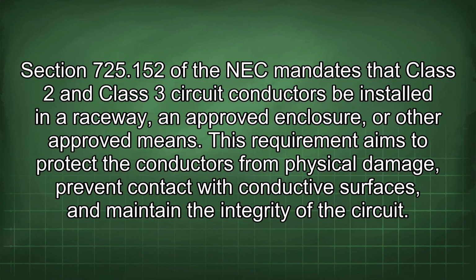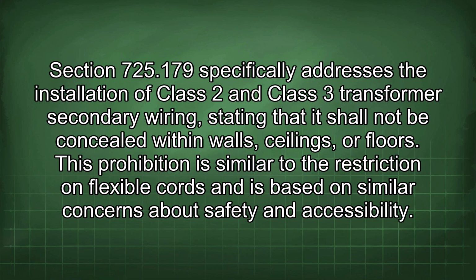Section 725.152 of the NEC mandates that Class 2 and Class 3 circuit conductors be installed in a raceway, an approved enclosure, or other approved means. This requirement aims to protect the conductors from physical damage, prevent contact with conductive surfaces, and maintain the integrity of the circuit.